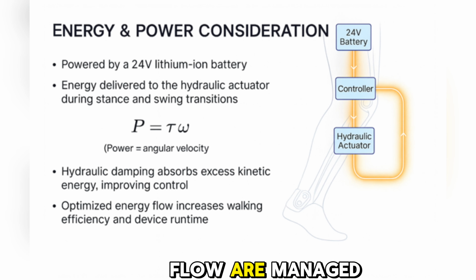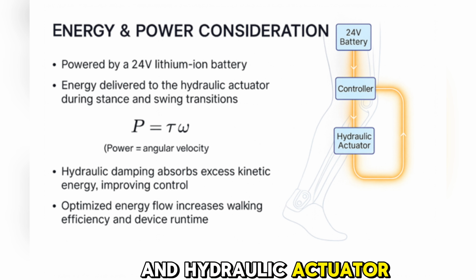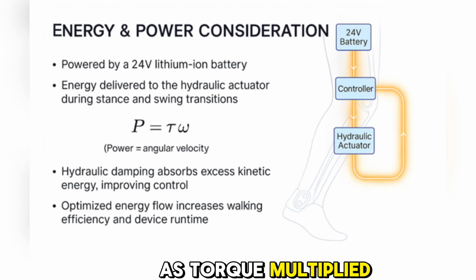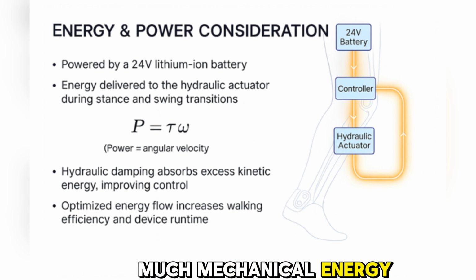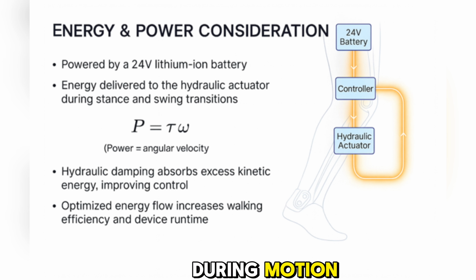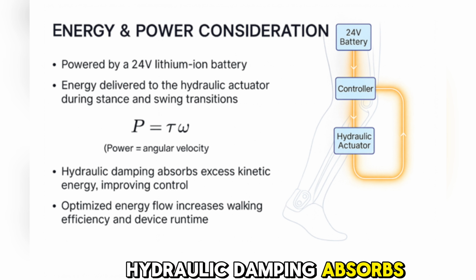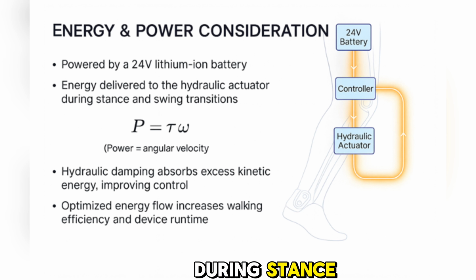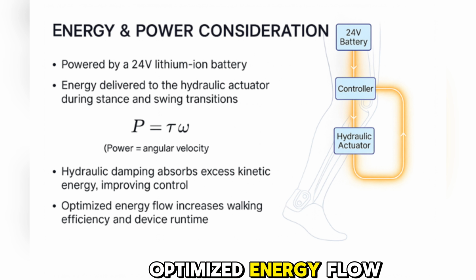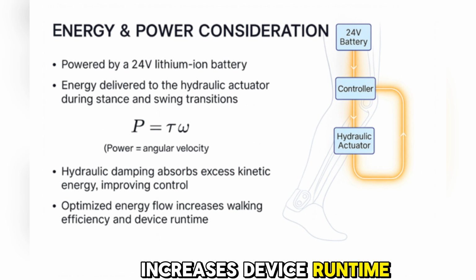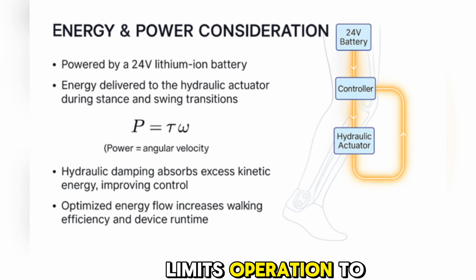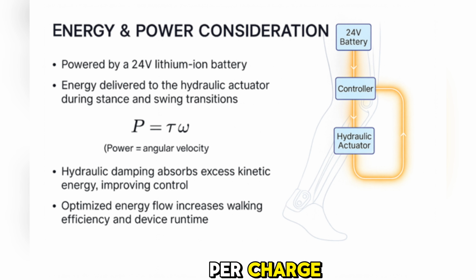Energy and power flow are managed by the 24-volt lithium-ion battery, which supplies current to the controller and hydraulic actuator. Power is defined as torque multiplied by angular velocity. This describes how much mechanical energy is being transferred at the knee during motion. Hydraulic damping absorbs excess kinetic energy during stance, improving control of deceleration. Optimized energy flow increases device runtime, though battery capacity limits operation to 6 to 8 hours per charge.